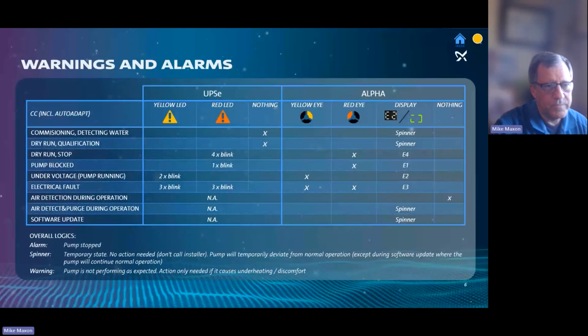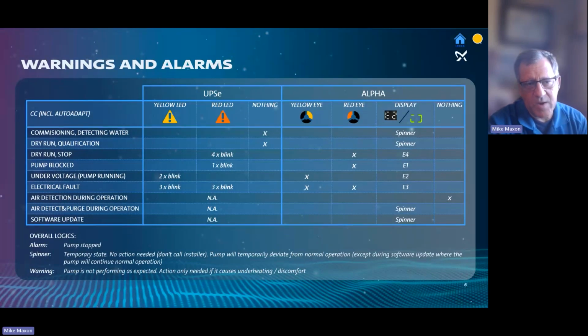For that error log on the UPSe, it's a little triangle. It'll be yellow if it's an alarm or warning, red if it's an alarm, and when it's red the pump is stopped. It will tell you what the error is by blinking. 4 blinks is a dry run. If it's red, 2 blinks, it's under voltage, yellow. Now on the Alpha, the Grundfos eye will change color to either the yellow or the red, and it will give you an error code on the numeric display.